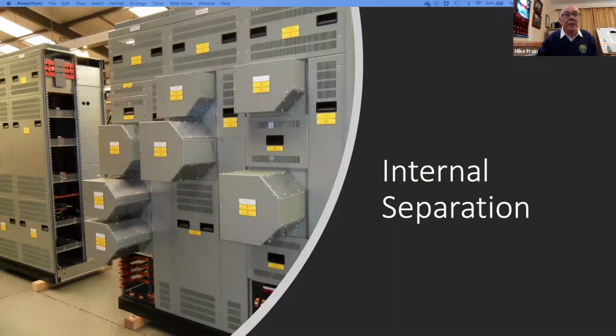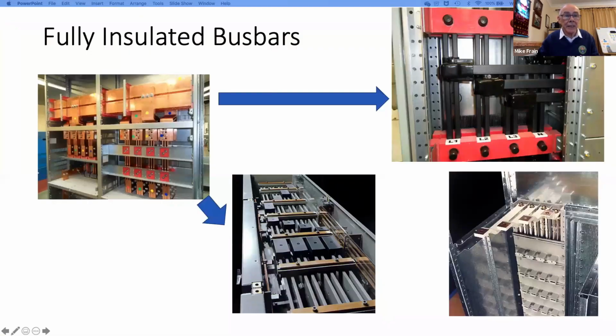So I'm going to just flick through one or two photographs of prevention techniques, internal separation, and this particular board, the outgoing device that are brought out to external cable boxes, so there's insulation and barriers between the outgoing terminals and the bus bars within the units themselves. Fully insulated bus bars, while on the left-hand side they're not insulated at all. Doesn't take much imagination to see that an arc flash, particularly if there's vermin that gets in there, is far more likely on the left-hand side than it is on the right-hand side.